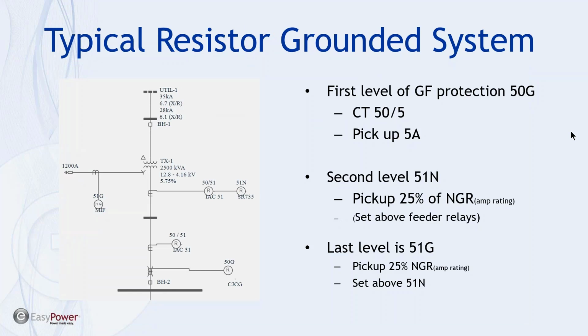So a typical resistor grounding system has basically multiple levels or zones of tolerance or overlapping protection. First of all, when we're looking at our first level of protection, it basically relies on the function of the 50G relay we have at the bottom, in this case detecting through a zero sequence CT, and its sensitivity can be gauged based upon what we want to tolerate as far as a continuous low-level ground.